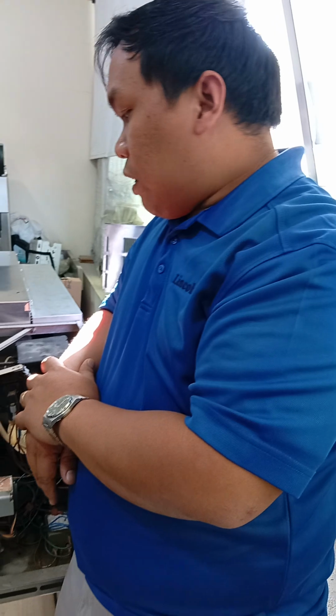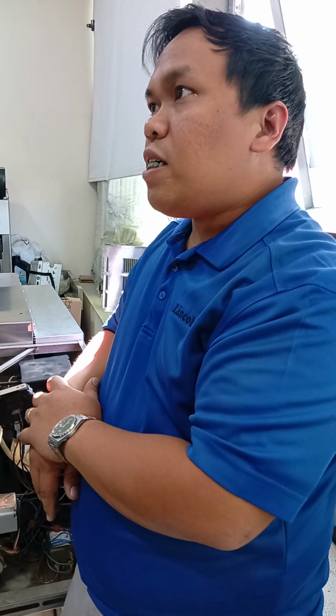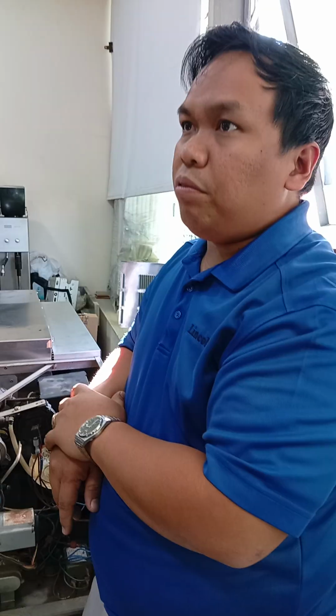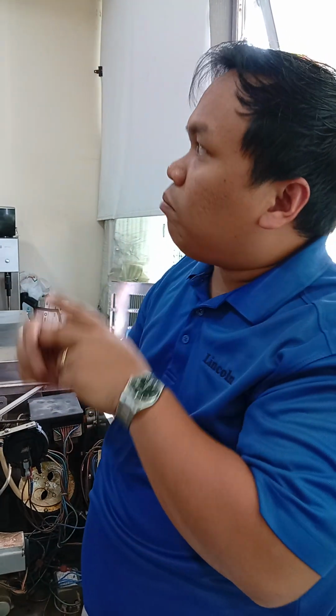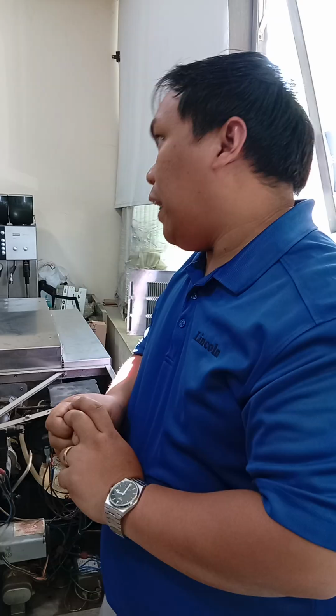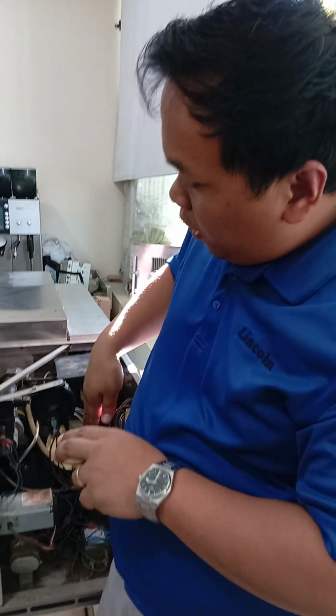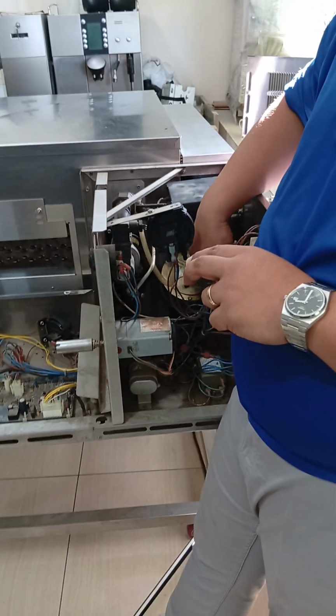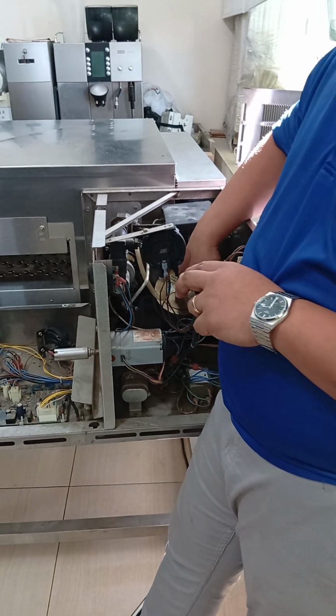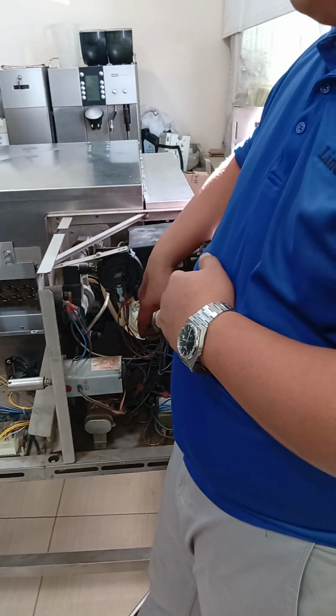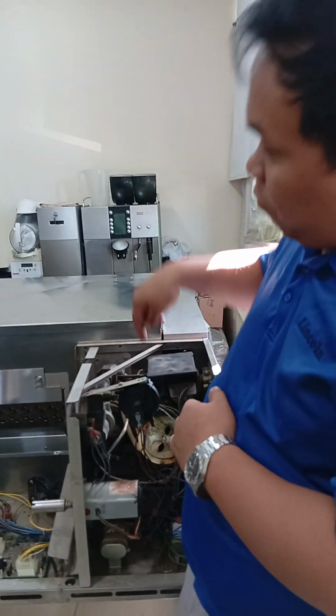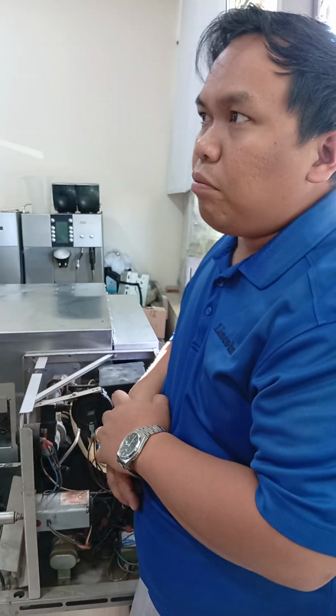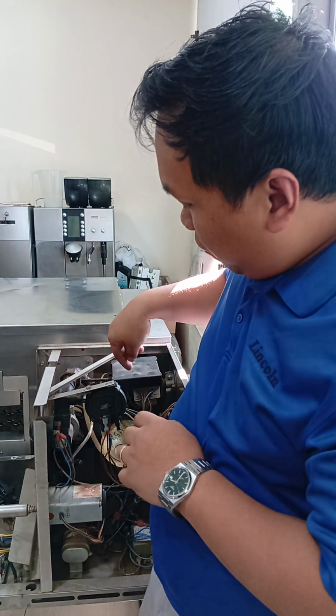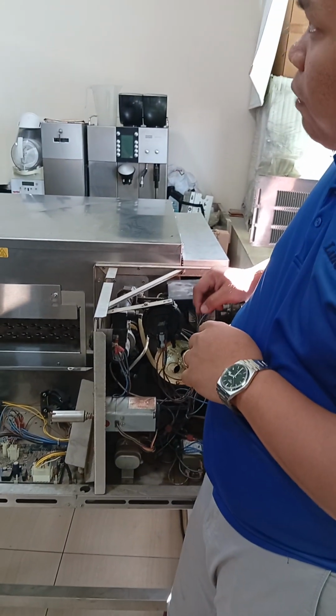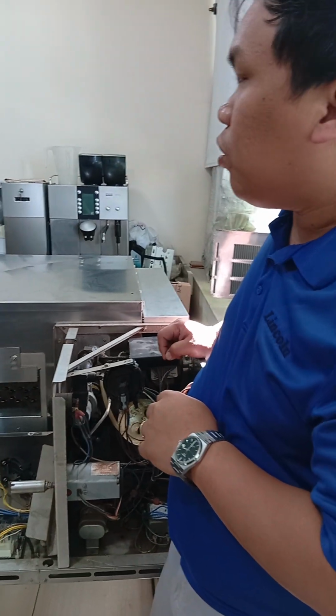What are the things that need to be cleaned? Inside, what you will verify is the electrode or ignition. Sometimes it starts to create some carbon. That you will clean. For the blower as well, you need to clean. Since you have every 3 months for gas, then inspect. If needed, you should dismantle. Okay. So if some of the wirings need to be replaced, you need to put it on your checklist.